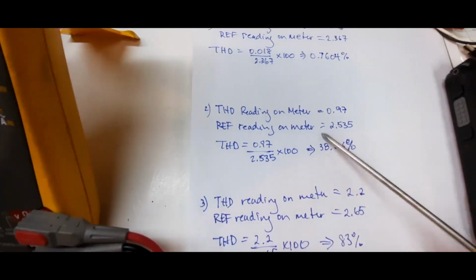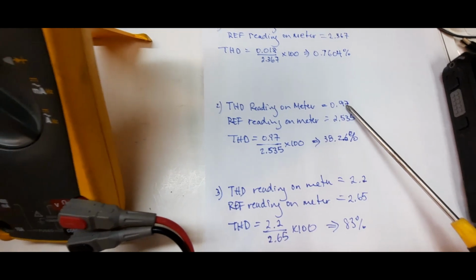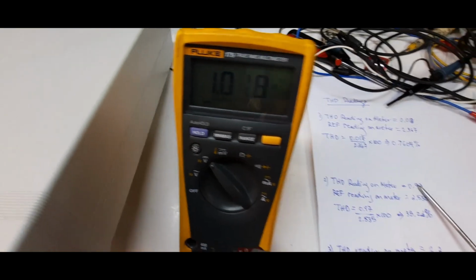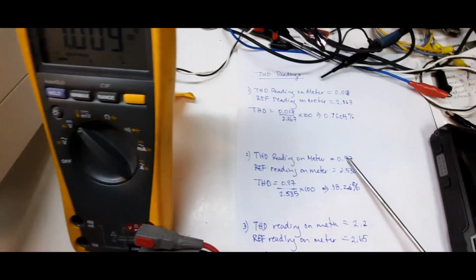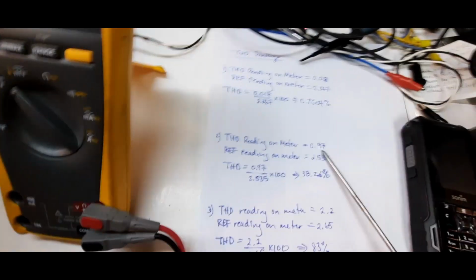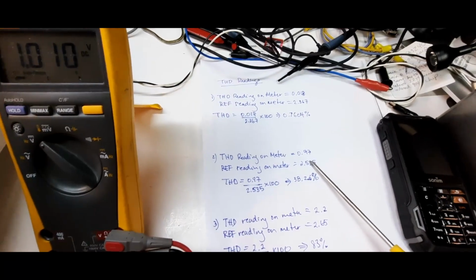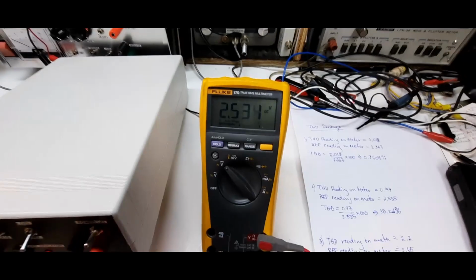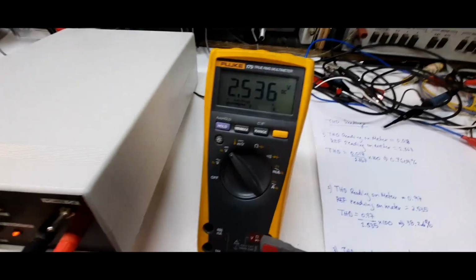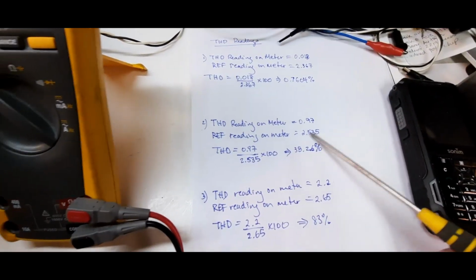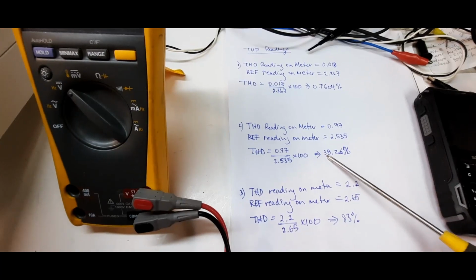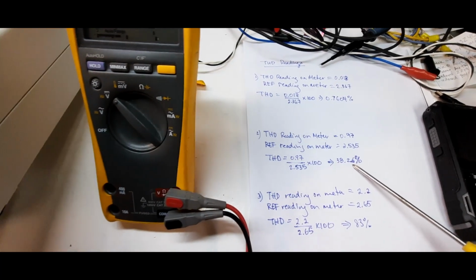So to get the THD again, you get the actual number from the meter - it's 1.03 or whatever, 0.97 I measured earlier. And the reference voltage is 2.536, that number stayed steady. If you do the math, we get about 38% distortion.